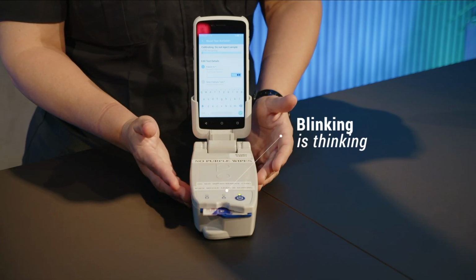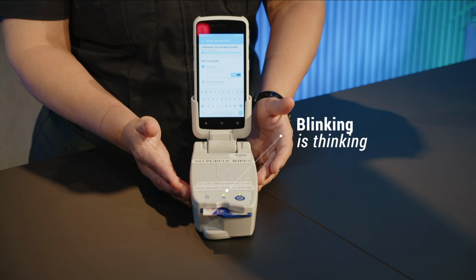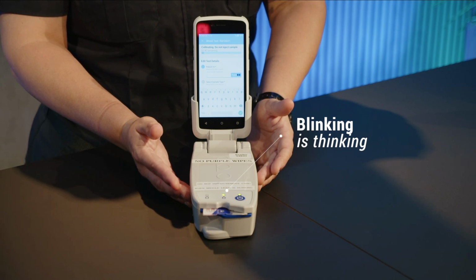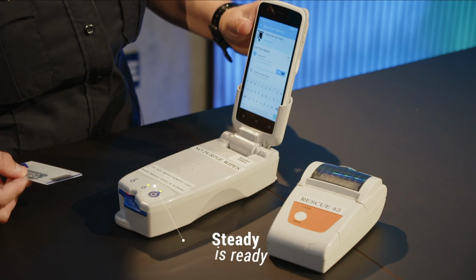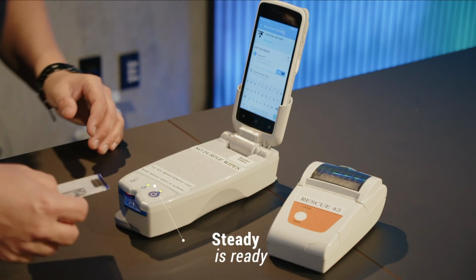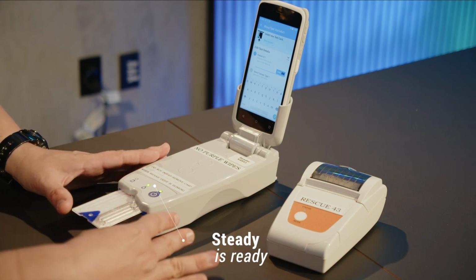If you notice the middle light on the reader is flashing, that just means the reader is processing and a small pin is extended to make contact with the test card. If a test card is inserted or removed while the pin is extended, the pin will be damaged and that causes the reader to become inoperable. The only time it's safe to insert or remove a test card is when the middle light is steady. So to remember this, we say, blinking is thinking, steady is ready.